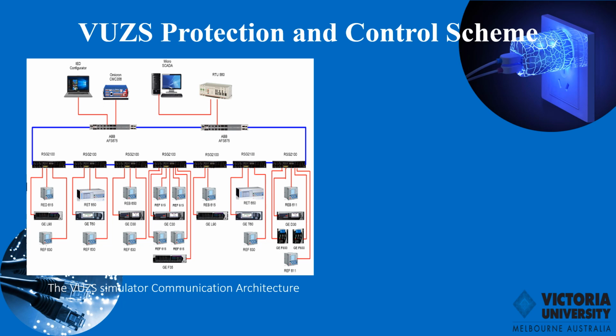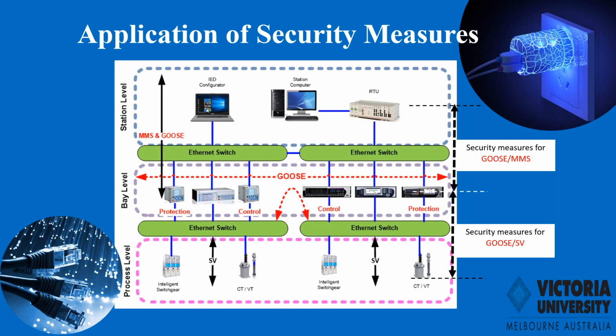It will focus more on the station bay level for the transmission of GOOSE and MMS protocol, while the sampled value on the process level will be produced by test devices like Omicron, Doble, and digital equipment like Opal-RT and RTDS. And this will emulate the characteristics of CTs and VTs in the substation. The application of security measures: security measures for GOOSE and MMS are between the station and bay level, and the security measures for GOOSE and sampled value are between the process level and bay level.